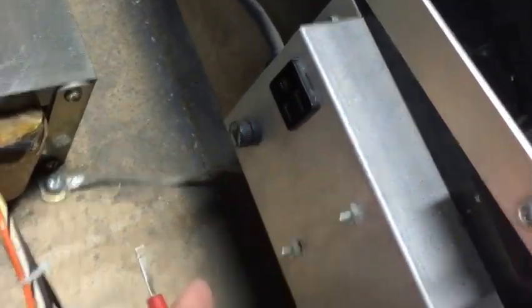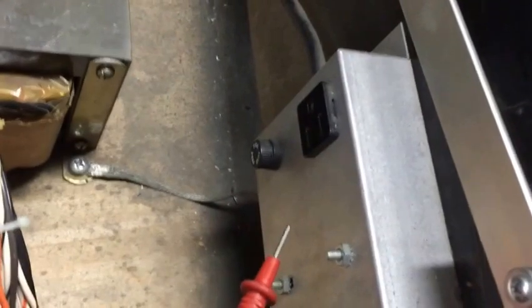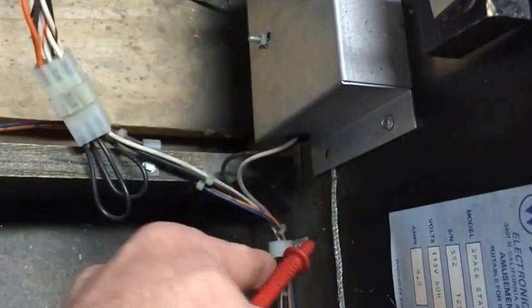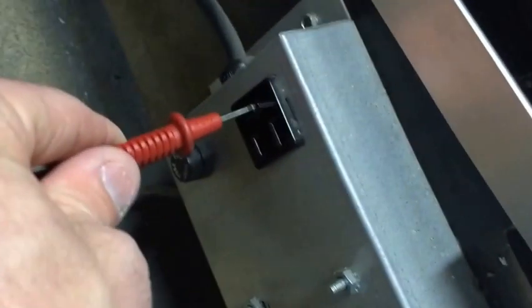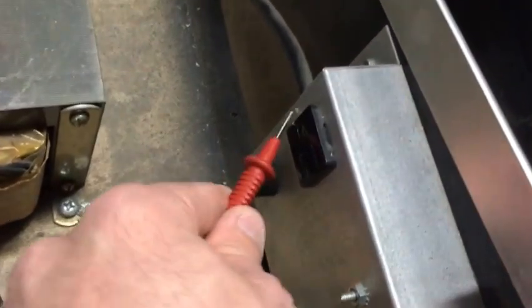Here's where the AC power comes into the machine, and it goes into this box, which has a utility outlet and a fuse. When I touch this metal anywhere on this ground braid, or the metal of this box, or the ground pin on this plug, I should be getting continuity. It should show a continuous circuit, and you can see pretty quickly that there's not.